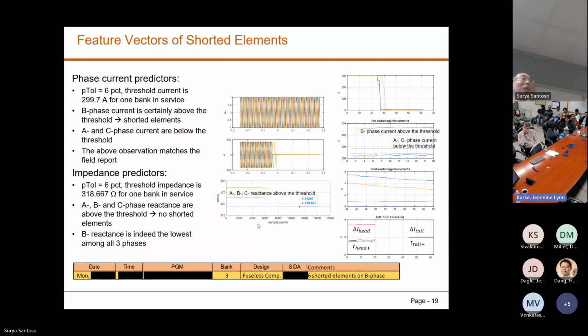So there are two competing feature vectors: impedance predictor or phase current. You see this is the waveform. We calculate the impedance - calculating impedance is not difficult. It's simply voltage divided by current, making sure that if the current is 0, you don't do the division, because that will create a NAN. So I just put NA there. You see in here, these are the impedances for A phase, B phase, and C phase.